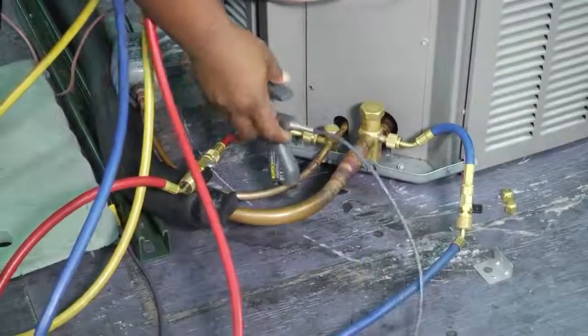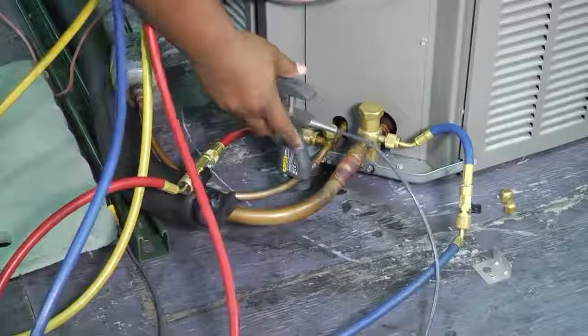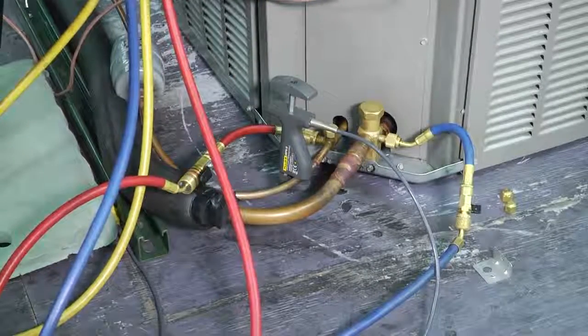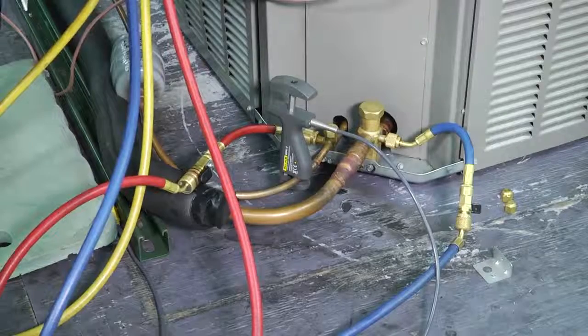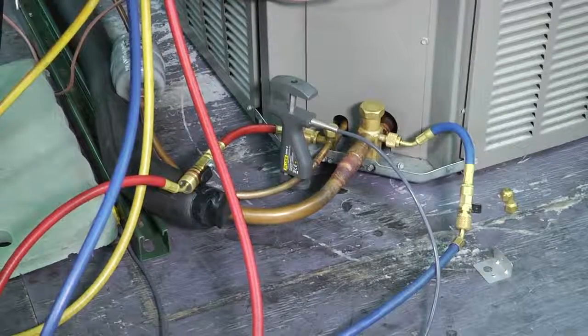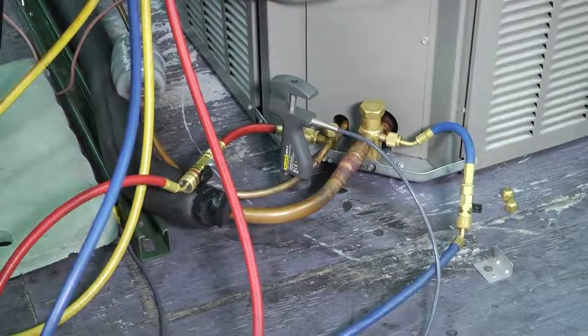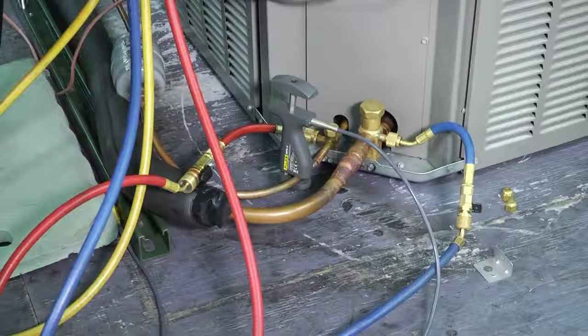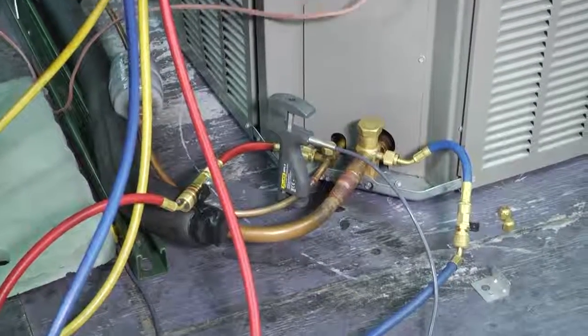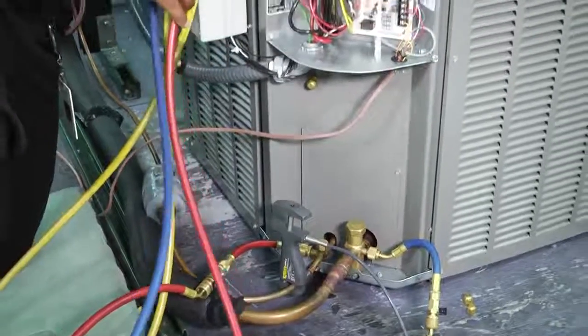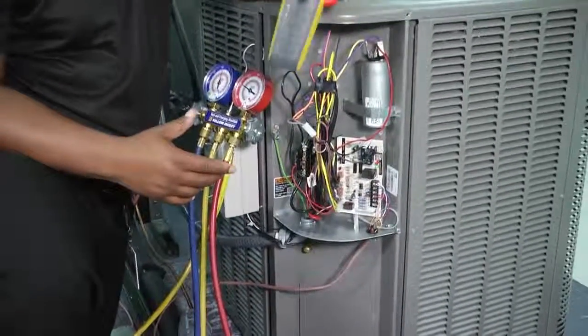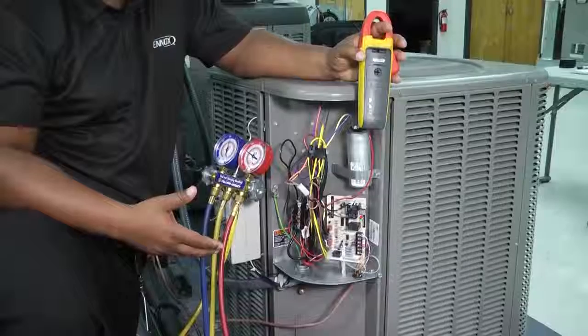You have my temperature clamps there. You'll want to put these in a good place and make sure that you catch it before a bend if you can. Sometimes, depending on how the condenser unit was installed, that's not possible, but you also want to take a look at that. All right, but anyway, we'll have our temperature clamp set up, we got our gauges set up, and now we're going to calculate superheat and subcooling.